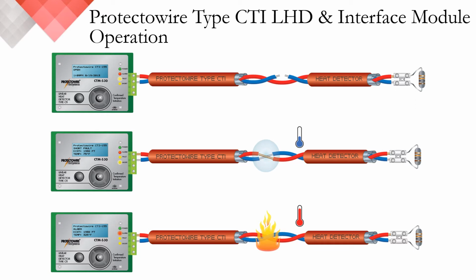And lastly, in the bottom image, similar to our standard PHSC technology, when the detector is exposed to heat at or above its set point, the CTM series module initiates an alarm condition. The module will then also actively display the temperature and location of the fire or overheat.